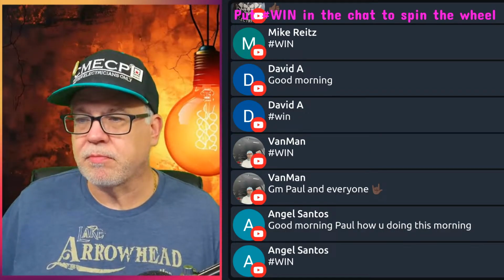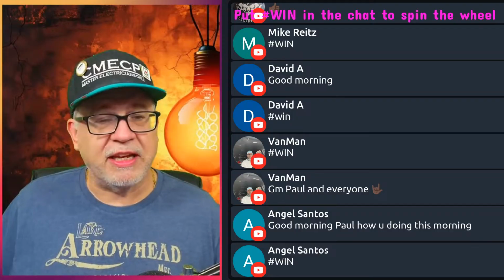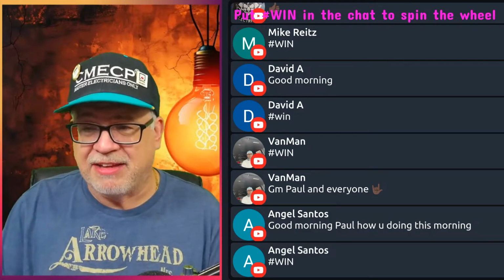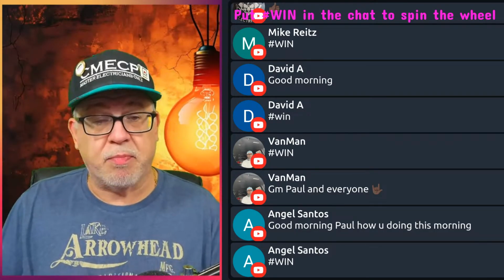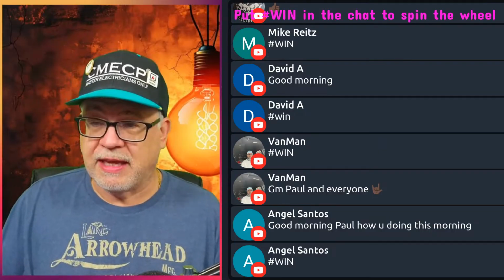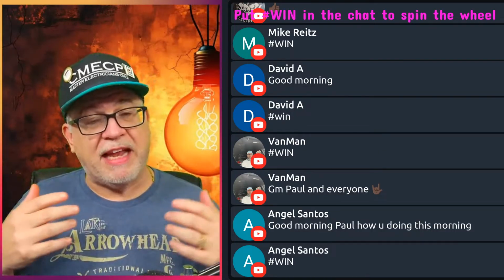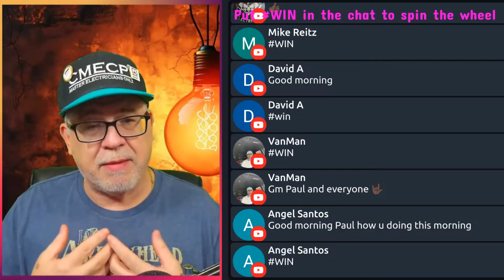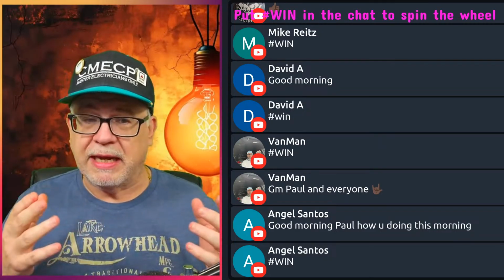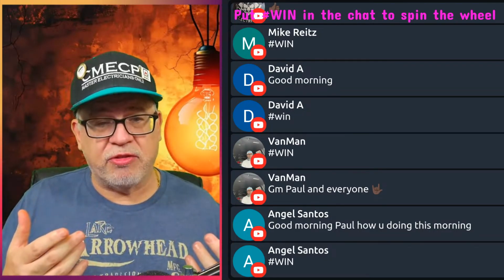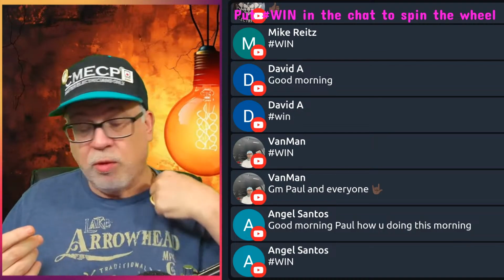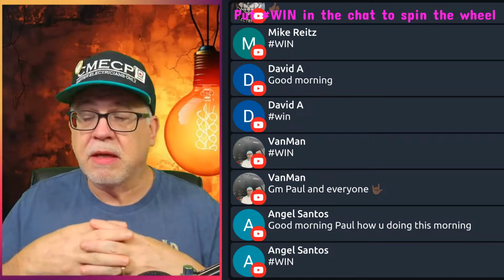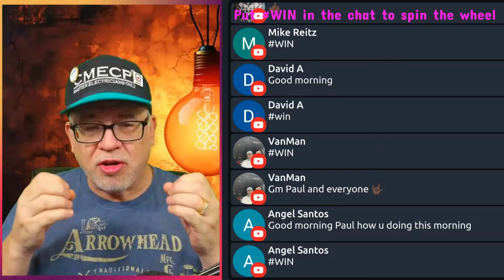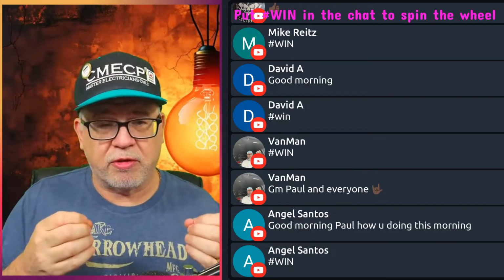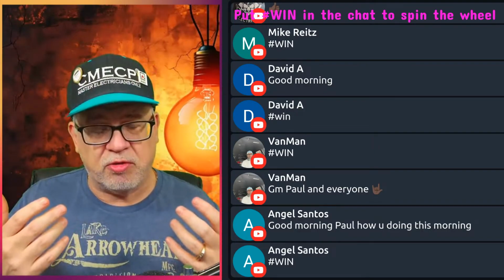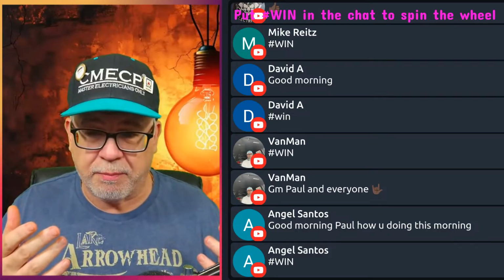Okay. All right. Let's look at another. So another change that took place has to do with those 10 amp branch circuits. One of the things, in order to make sure that we don't put this, that's the one problem I have with a 10 amp branch circuit. Y'all heard us talk about it. When you introduce a 10 amp branch circuit in smaller conductors, which will probably make it into the NEC this time, you can only put certain loads on those 10 amp branch circuits. And it was intended for lighting type of loads. You can't put receptacles on those 10 amp branch circuits.